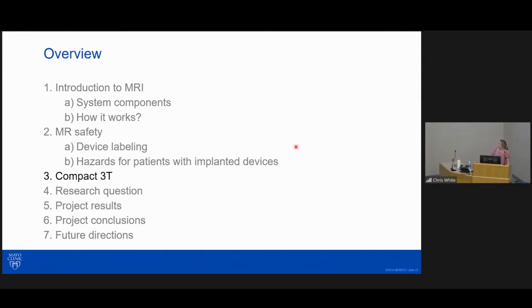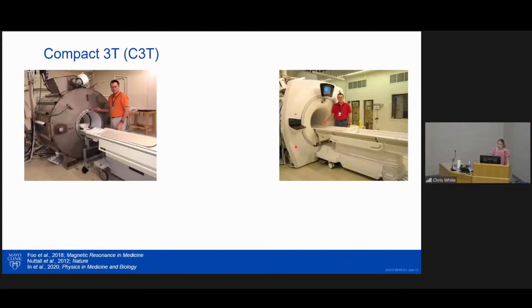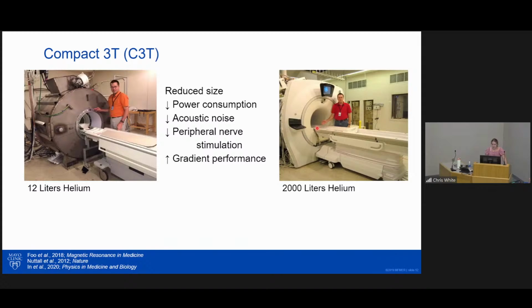So next, I'm going to give some background on a compact 3T scanner. So a compact 3T scanner was developed as an NIH-funded collaboration with Mayo Clinic and GE Research in New York as a technology demonstrator. The compact 3T is not FDA approved, so it is a research-only scanner. The figure shows the size of the compact 3T on the left compared to the size of a whole body system on the right. The compact 3T uses 12 liters of liquid helium compared to 2,000 liters in a whole body system. And this is important because helium is a non-renewable resource that is in short supply.